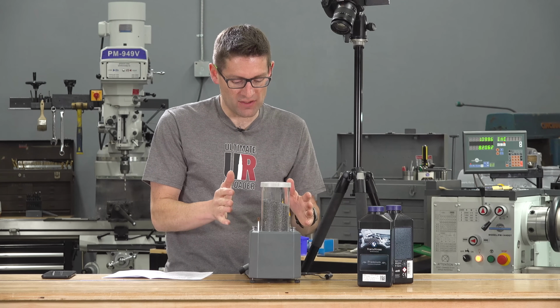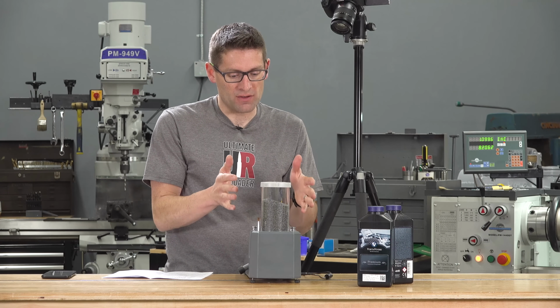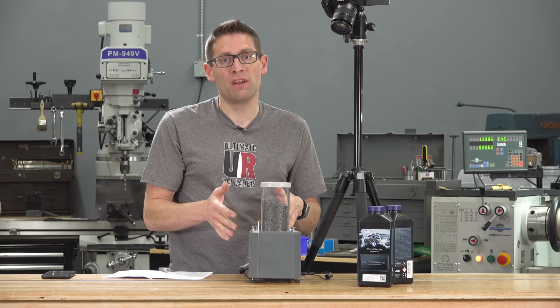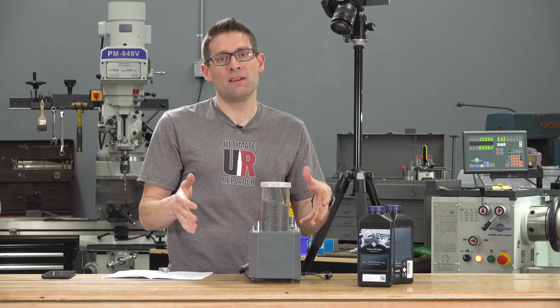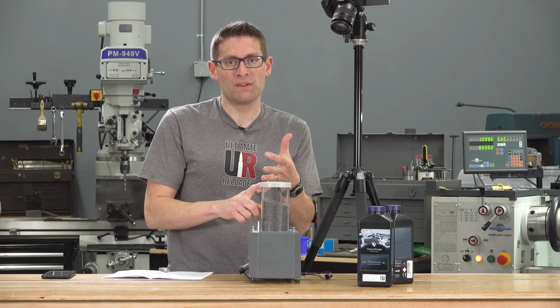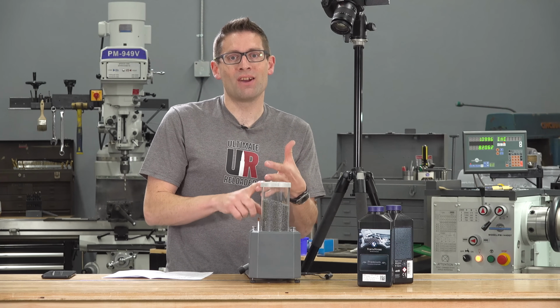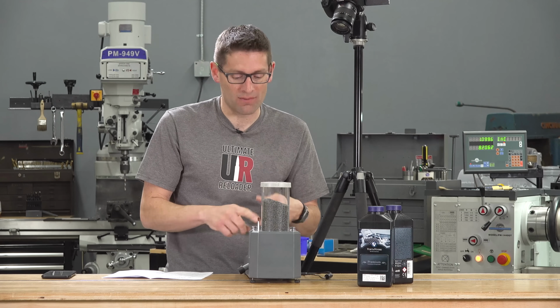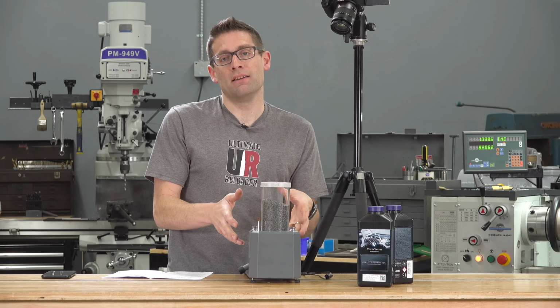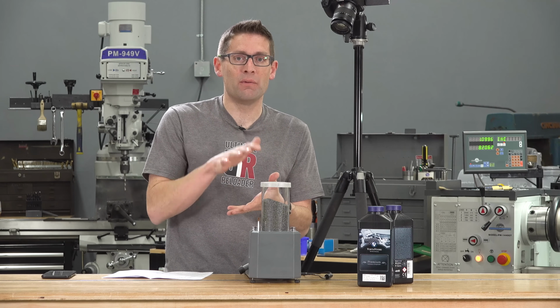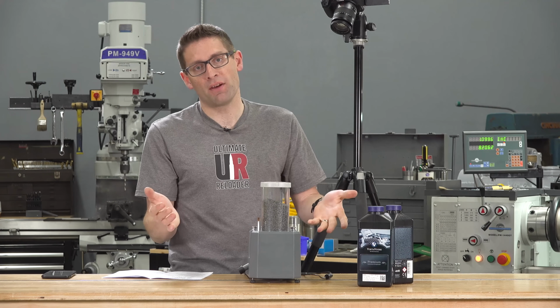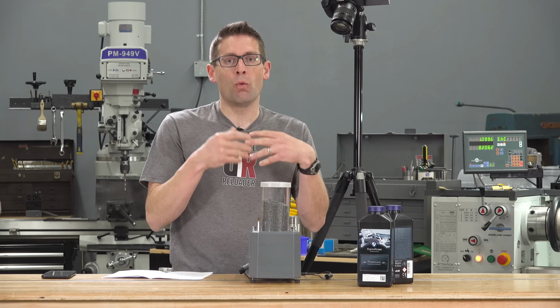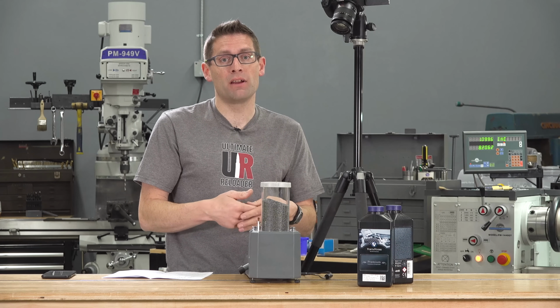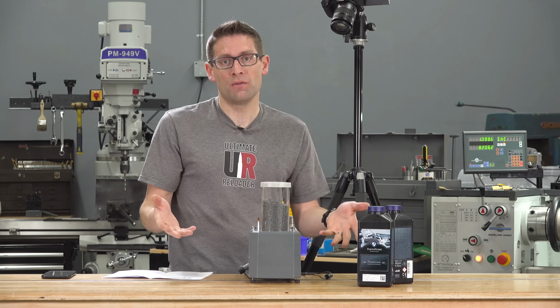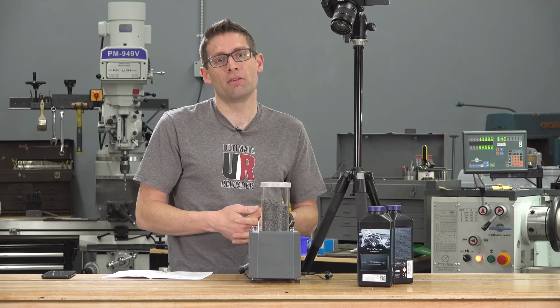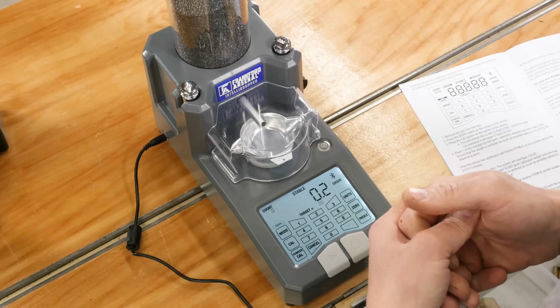And like I said, you need to level the dispenser. You need to calibrate the dispenser. I just ran the powder calibration routine that's going to optimize our speed. But we also need to be very careful about temperature fluctuations in the room, and make sure that air is not hitting the platen and the pan, like from a fan or from an HVAC system. Because if it does, it's going to influence the reading of the scale, and that's going to throw everything off. So the cover helps with that, and letting the unit warm up helps with that. I usually calibrate a scale like this every time I go to do a loading session, and I give it at least half an hour to warm up. Longer is not a bad idea, actually.